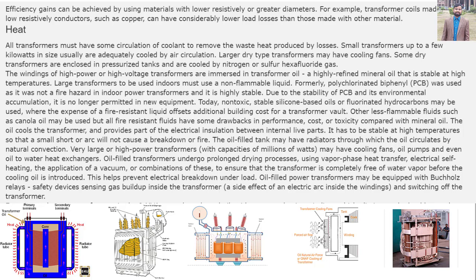Other less flammable fluids such as canola oil may be used but all fire-resistant fluids have some drawbacks in performance, cost, or toxicity compared with mineral oil. The oil cools the transformer and provides part of the electrical insulation between internal live parts. It has to be stable at high temperatures so that a small short or arc will not cause a breakdown or fire. The oil-filled tank may have radiators through which the oil circulates by natural convection.